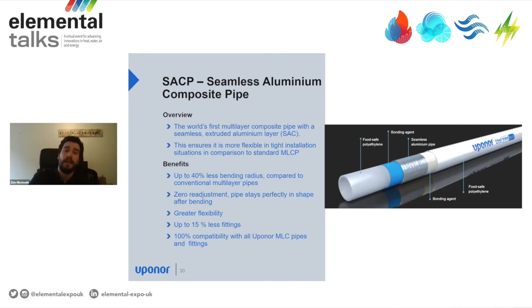It is the first multi-layer composite pipe in the world to come with a seamless extruded aluminium layer within the pipe structure. This aluminium layer ensures great flexibility and up to 40% less bending radius compared to common MLC pipes. The pipe doesn't require any readjustment during installation, as it stays in shape after bending. This greater flexibility leads to installation with up to 15% fewer fittings, reducing installation times and lowering the risk of leaks.